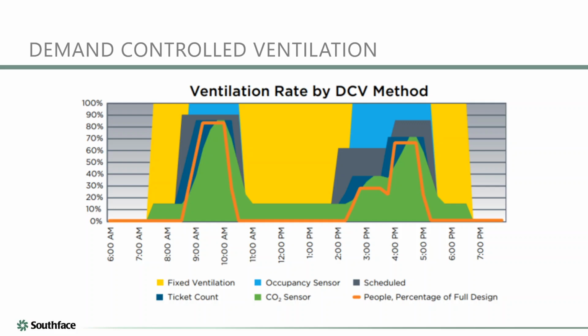The chart does a great job of showing you're required to do this outside air, this ventilation in commercial buildings. If you don't have any control, you basically have to ventilate at full rate all the time. So you see that big yellow block. There is a lot of energy savings and cost savings associated with matching your ventilation load to your people load. And ventilation is essentially for people. So what we're able to do here is you see our orange bar of people showing how the load of people is moving through this space throughout the day. And by having these demand-controlled ventilation functions, we're able to match the ventilation in the room to the load of people, and in doing so, save a lot of energy and save a lot of dollars.